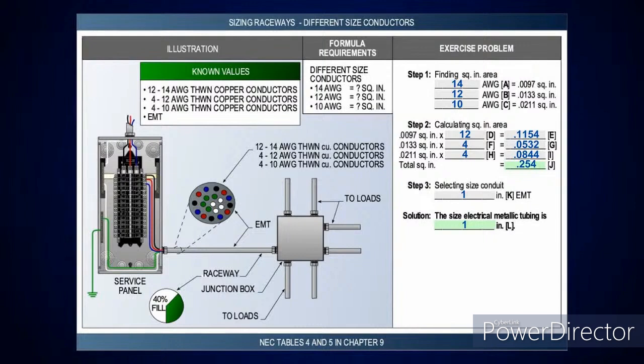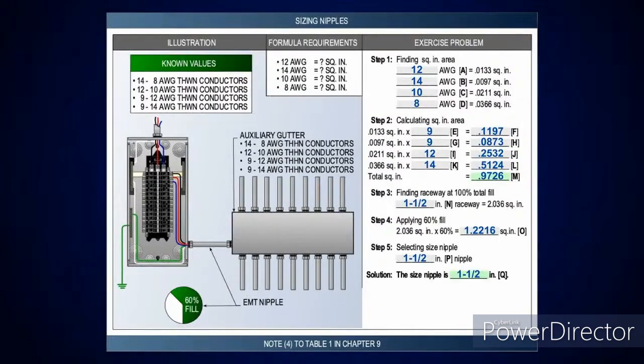Come across to the left and it tells you that you need a 1-inch EMT. Very simple to follow. I want to point out the 40% fill on that raceway — if you were to shorten it to 24 inches or less, then you could do up to 60% fill. That's going to be on the next example.